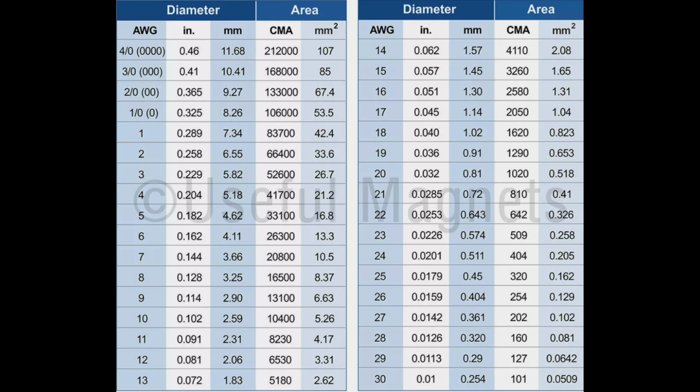For example, I recently did a job where somebody had sized their cable in millimeters diameter, but the calculation for the instructions had been done in cross-sectional area, millimeters squared. There's a big difference. You can get apps for your phone or look up on the internet what the maximum cable run you can have in any particular size for the amperage that cable is having to carry. Hardly anyone does the calculation longhand anymore, using the resistance per meter in ohms for that calculation.